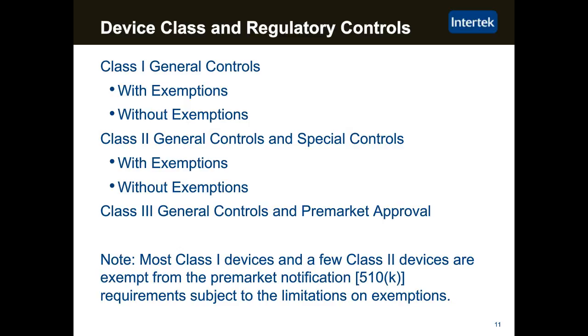So a Class 1 device with general controls can exist with exemptions or without exemptions. And here, when we talk about exemptions, it may be exempt from pre-market notification. It may even be exempt from compliance with good manufacturing practices. Then we look at Class 2. Class 2 devices have to be in compliance with general controls, but because they're higher risk devices, you'll also see special controls applied. And those are guidance documents from the FDA or harmonized standards. There are some low-risk Class 2 devices that also have exemptions, and they may be exempt from the pre-market notification requirement, and in a few cases also exempt from the application of good manufacturing practices.